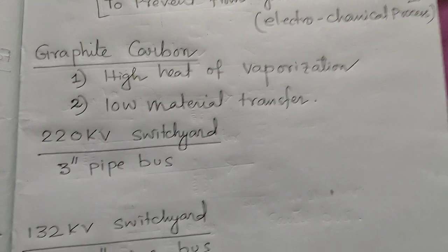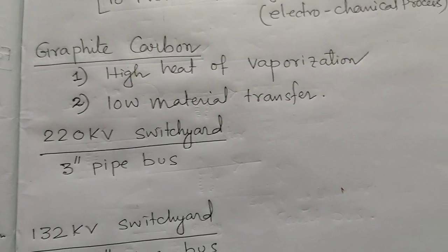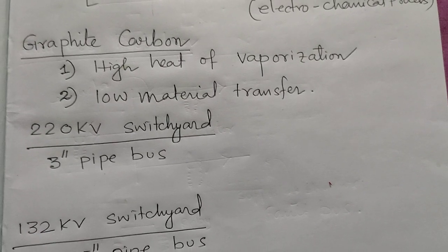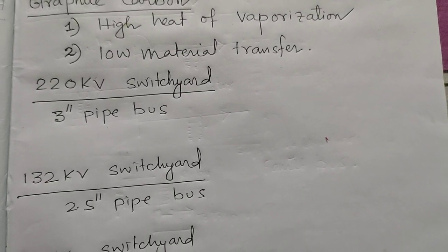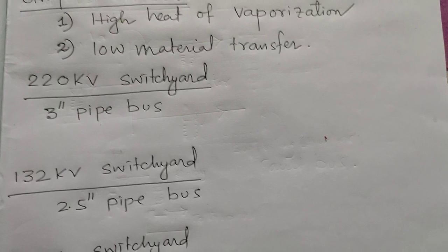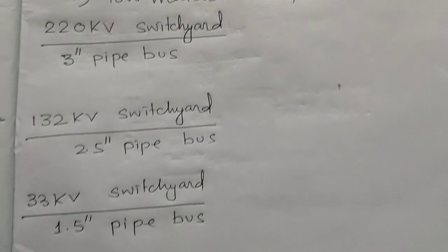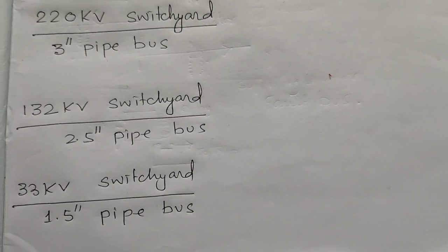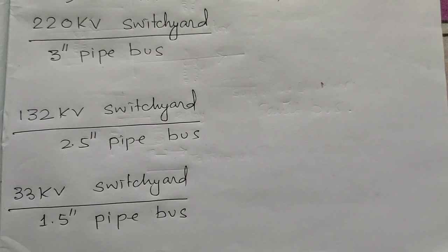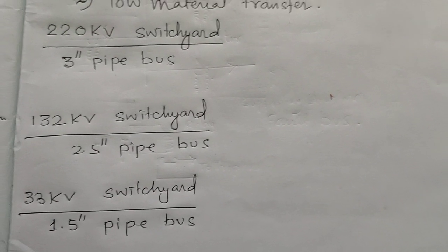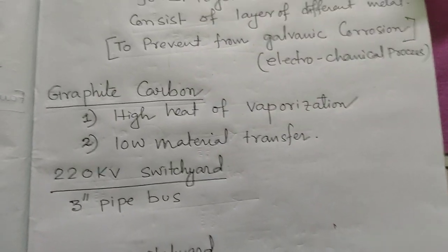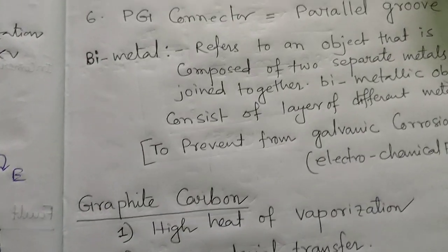In 220 kV switchyards, three-inch pipe buses are generally used. In 132 kV switchyards, two-and-a-half-inch pipe buses are used nowadays. In 33 kV switchyards, one-and-a-half-inch pipe buses are used. We have attached some pictures related to various connectors with their names.